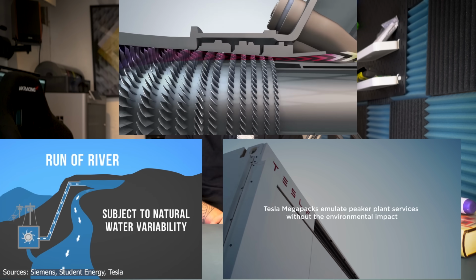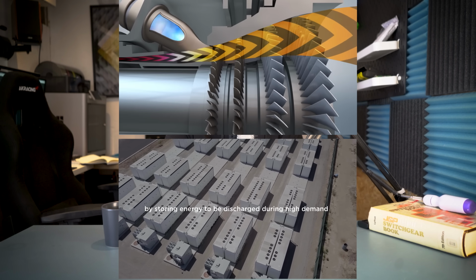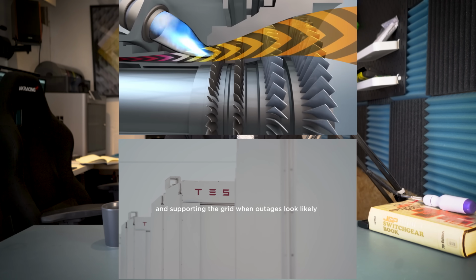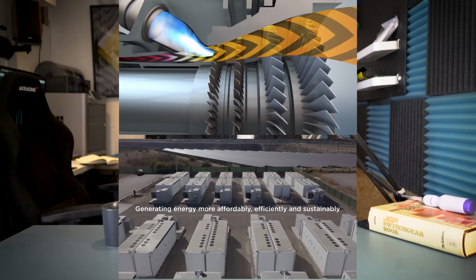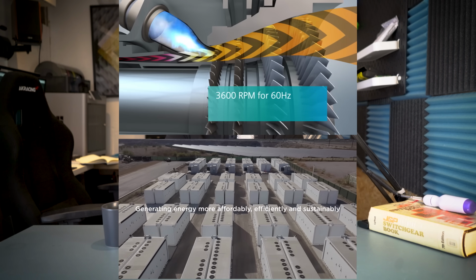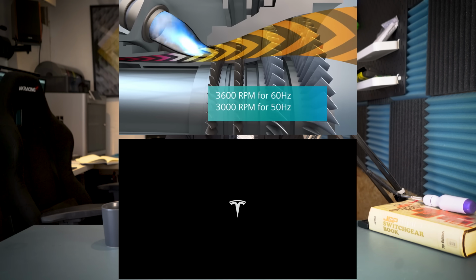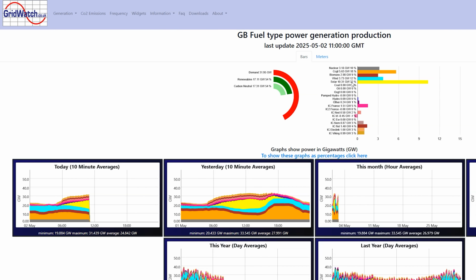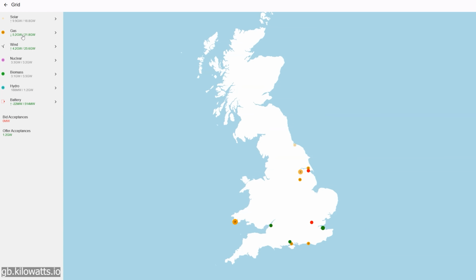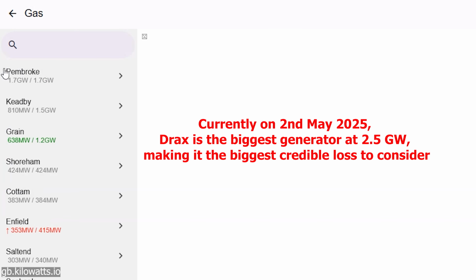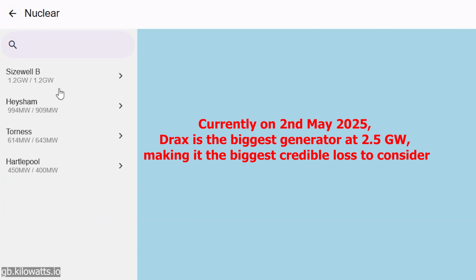And if that's not enough, secondary frequency response follows, adjusting generation or load within about 30 seconds. If the system still needs help, NESO calls on fast reserves, bigger backup sources or load reduction that can activate within 2 minutes. And finally, if necessary, NESO relies on demand turndown, agreements where large users like factories voluntarily shut off to help balance the grid. This takes a few more minutes, but it's a vital last line of defence. The entire reserve system is designed around what's called the largest credible loss, the sudden failure of the biggest single generator or interconnector, while accounting for how much spinning mass or inertia is online to stabilise the grid.